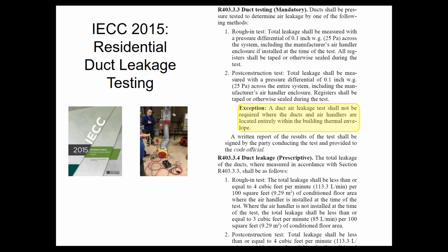The AeroSeal test is done at 25 pascals, just like this code test is. So it's essentially the same test. There's no reason they shouldn't accept it and make you have a separate one. Nothing really changed in the 2012 to 2015 code. The whole section looks different for this duct testing, but when I read it over and over, which I've done a dozen times now, it looks like it's the exact same wording to me. It's just reorientated. No real big change from 2012.